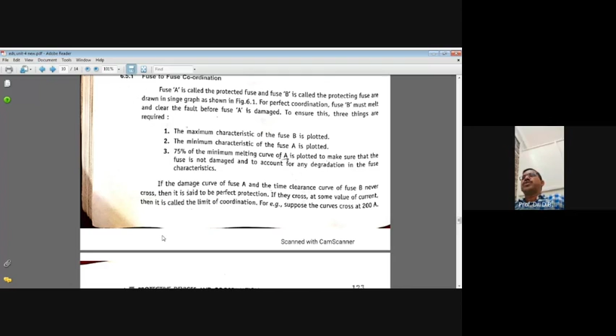I will repeat. Fuse A is called the protected fuse, and fuse B is called the protecting fuse, drawn in the single line diagram as shown in the figure. For perfect coordination, fuse B must melt and clear the fault before fuse A is damaged. To ensure this, three things are required: the maximum characteristics of fuse B is plotted, the minimum characteristics of fuse A is plotted, and 75% of the minimum melting curve of fuse A is plotted to make sure that the fuse is not damaged and to account for any degradation in the fuse characteristics.